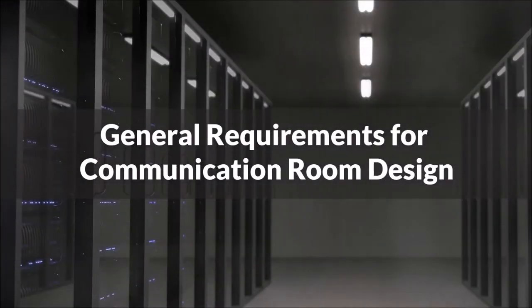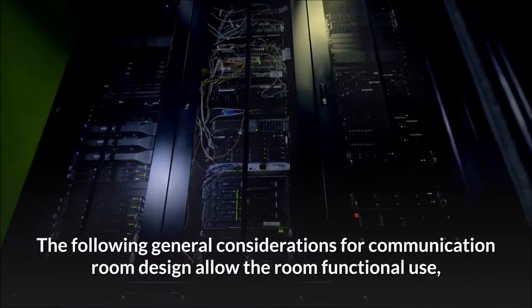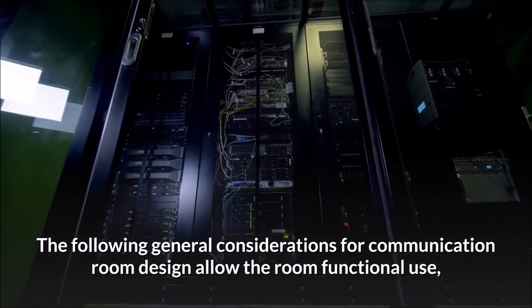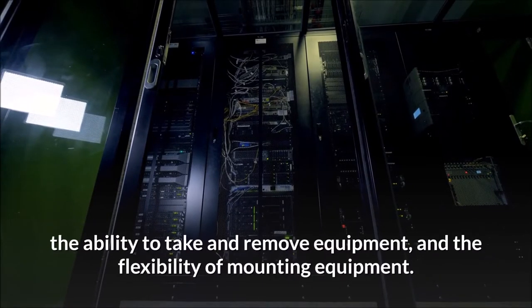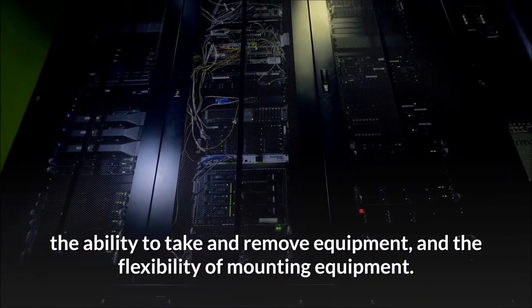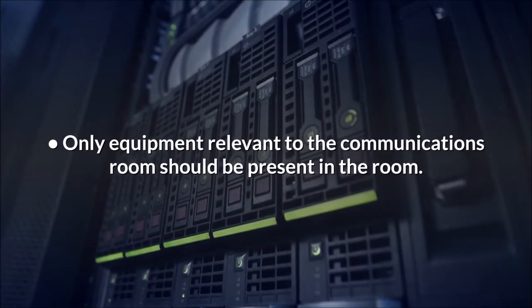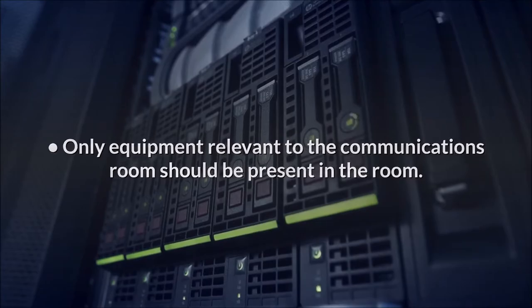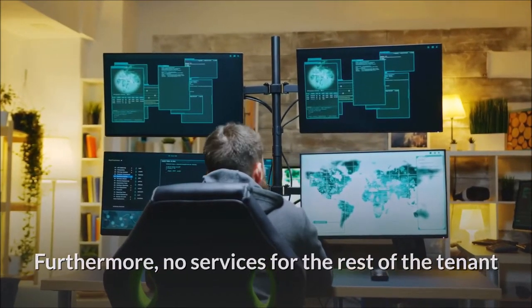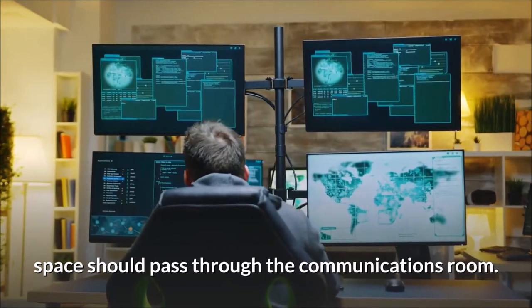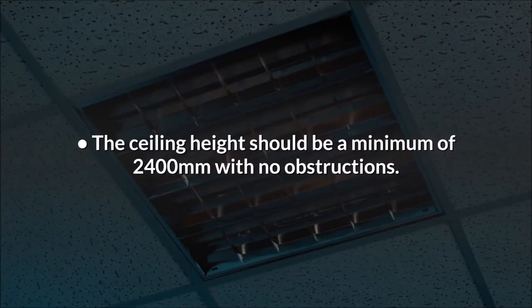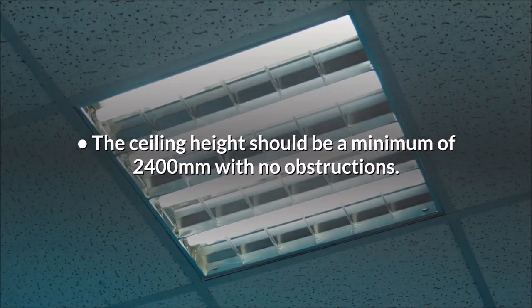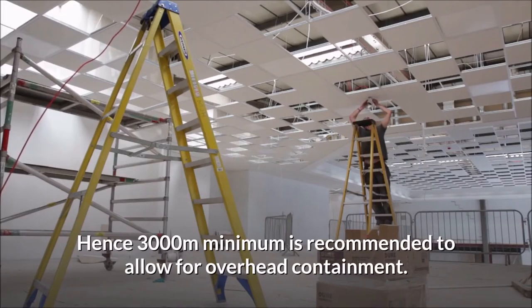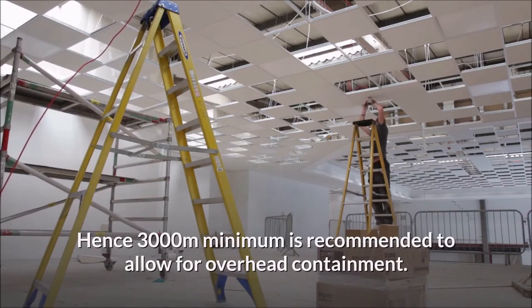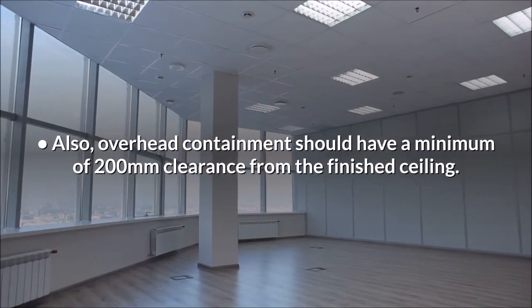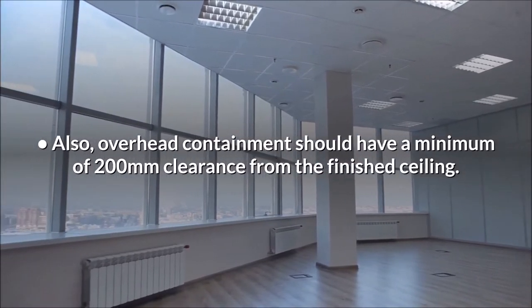General requirements for communication room design. The following general considerations for communication room design allow the room functional use, the ability to take and remove equipment, and the flexibility of mounting equipment. Only equipment relevant to the communications room should be present in the room. Furthermore, no services for the rest of the tenant space should pass through the communications room. The ceiling height should be a minimum of 2,400 mm with no obstructions. Hence, 3,000 mm minimum is recommended to allow for overhead containment. Also, overhead containment should have a minimum of 200 mm clearance from the finished ceiling.